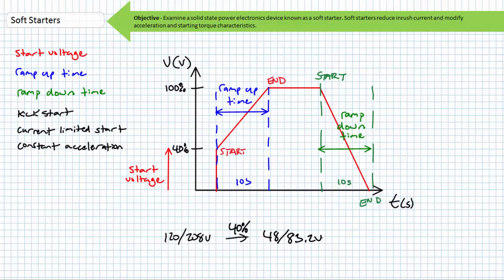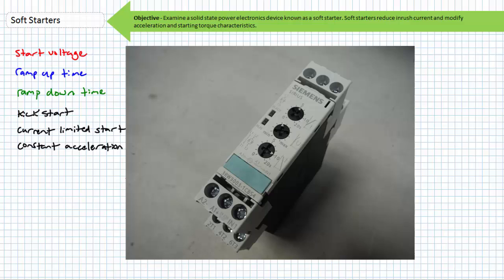The graph illustrates the soft starter would take 10 seconds to ramp down the applied voltage from full voltage to 0 volts upon loss of the input signal. This particular soft starter has 3 adjustable potentiometers to respectively adjust ramp-up time from 0 to 20 seconds, start voltage from 0 to 100%, and ramp down time from 0 to 20 seconds. Again, note, ordinarily soft starters avoid going below around 40% of full voltage, since anything less may not produce the current necessary to even move the rotor.